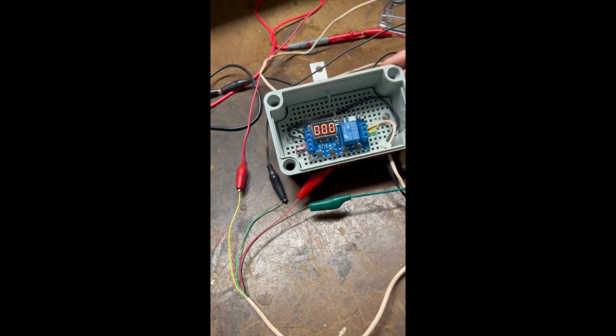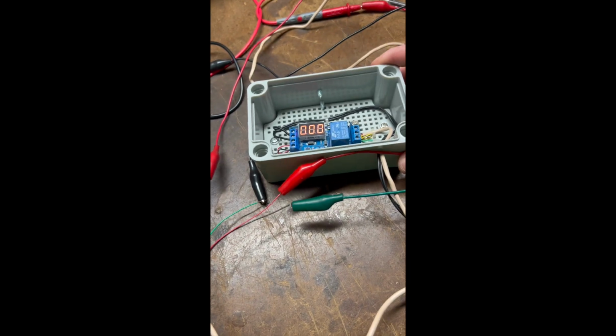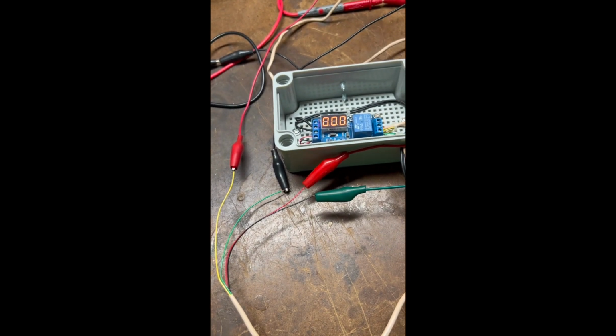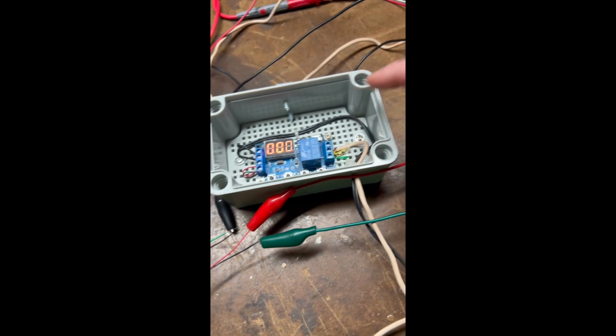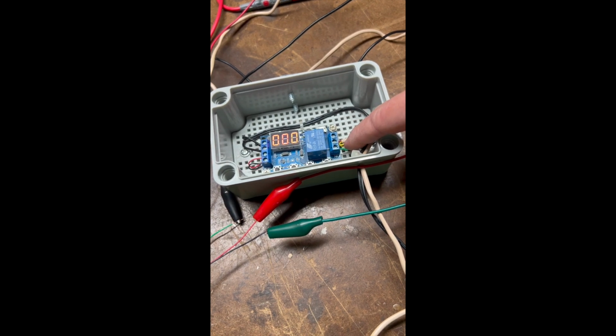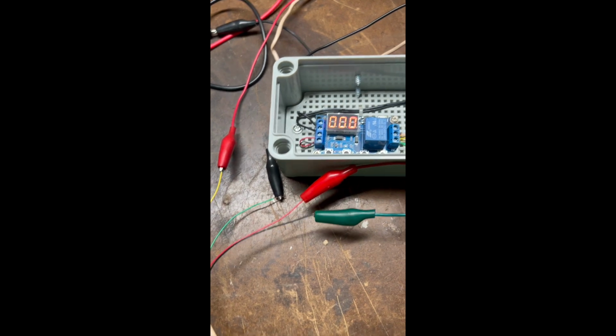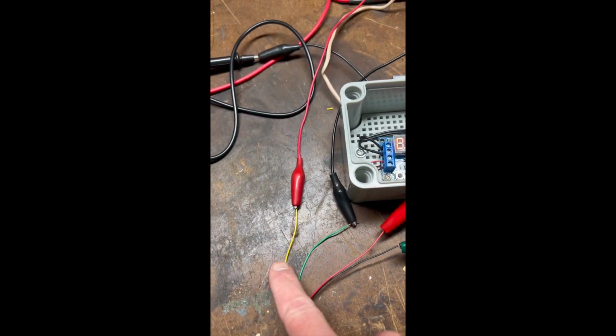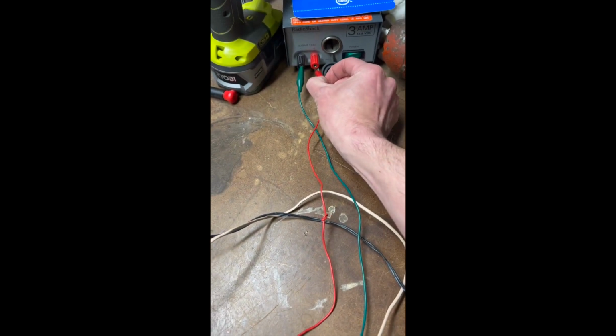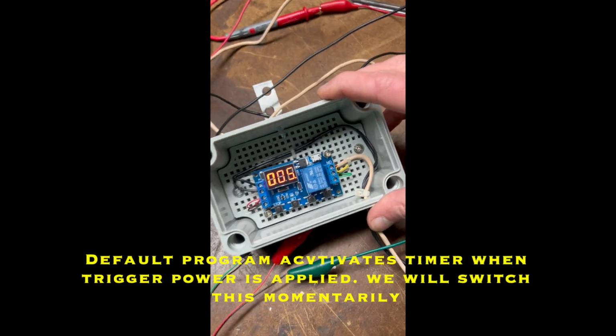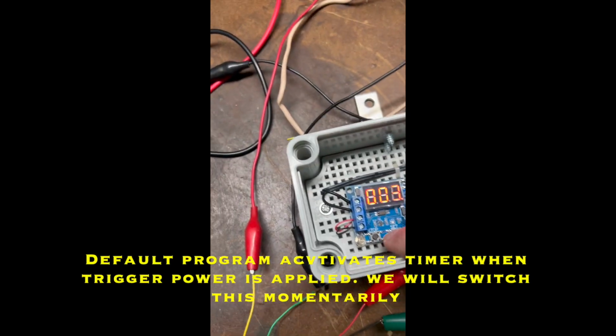We've got our unit hooked up. We've got it plugged in. I've got constant power coming in on this 12-volt power supply that I mentioned. Remember, I've got my green and yellow, my normally closed relay contacts. My black and red are my trigger voltage. I've got my relay contacts connected to this ohmmeter. I've got the trigger contacts connected to this 12-volt power supply. And right now it's actually counting down because it's in its default program.